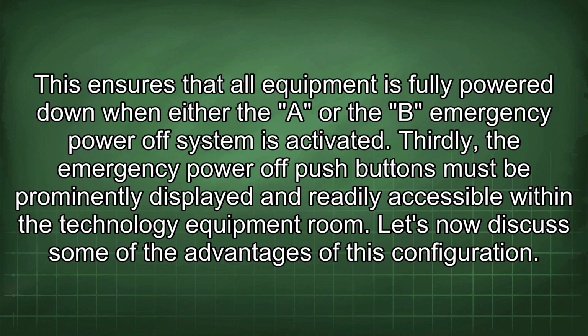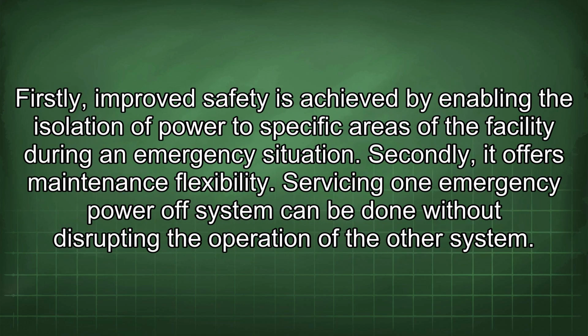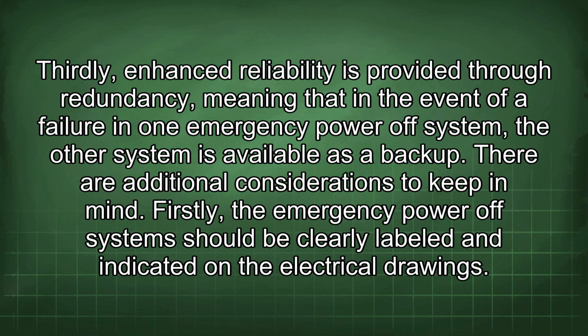Let's now discuss some of the advantages of this configuration. Firstly, improved safety is achieved by enabling the isolation of power to specific areas of the facility during an emergency situation. Secondly, it offers maintenance flexibility. Servicing one emergency power-off system can be done without disrupting the operation of the other system. Thirdly, enhanced reliability is provided through redundancy, meaning that in the event of a failure in one emergency power-off system, the other system is available as a backup.